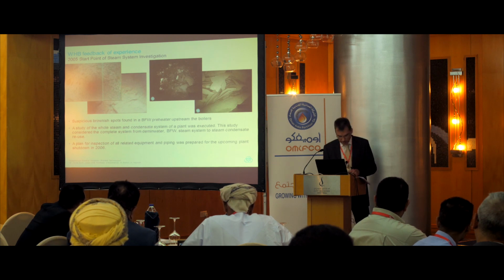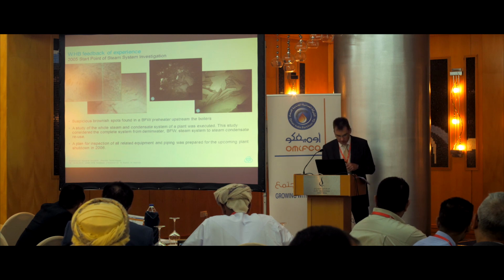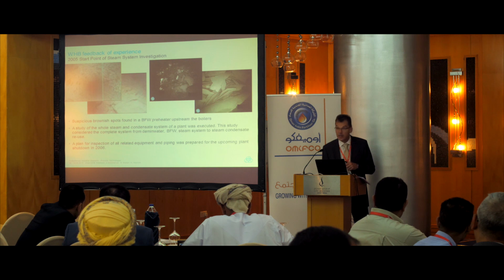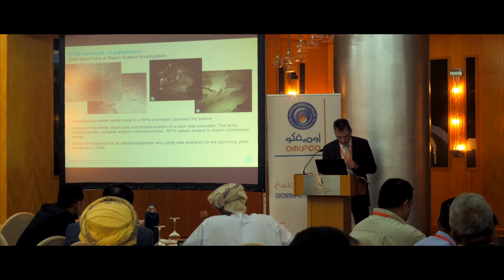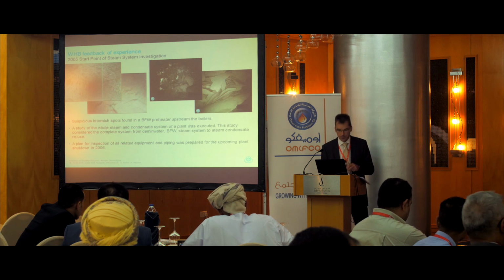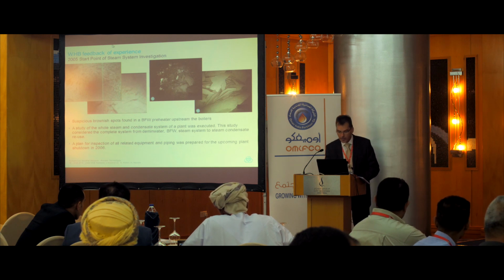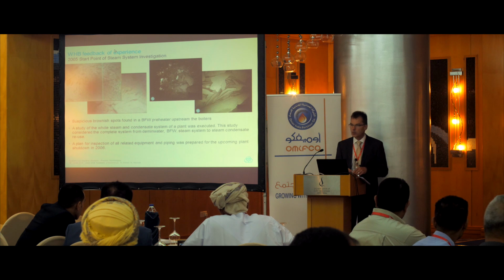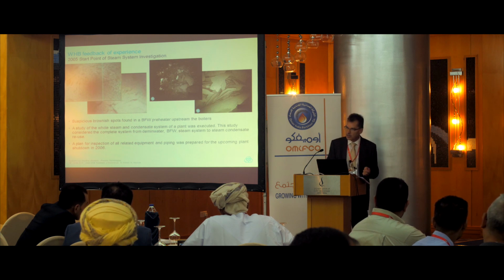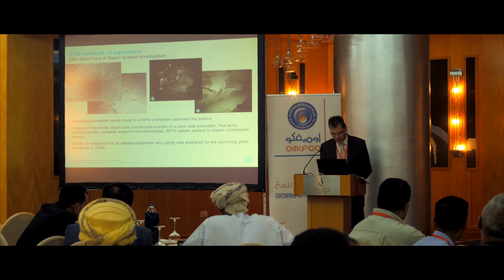All these recommendations were taken over to all new fertilizer plants from 2005-2006 onwards. In addition, an automated blowdown operated by DCS, independent from plant personnel, was requested in all new plants. This helps to avoid that blowdown is opened or closed just by accident when the operator is outside, and not by a real automatic plan.